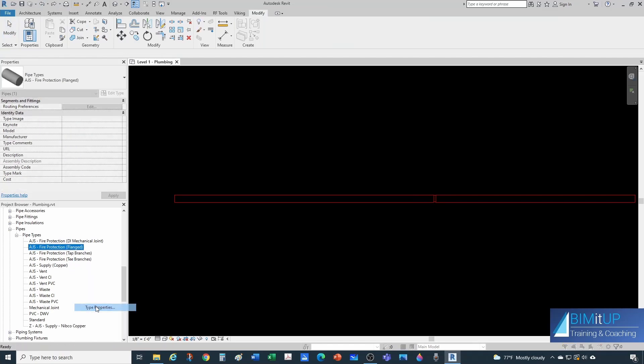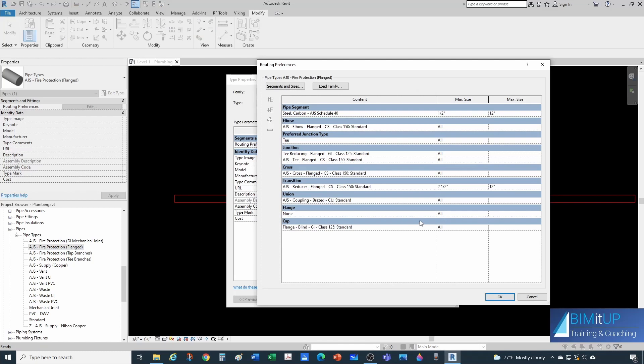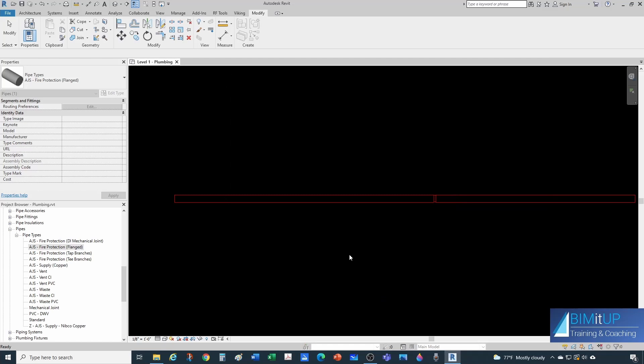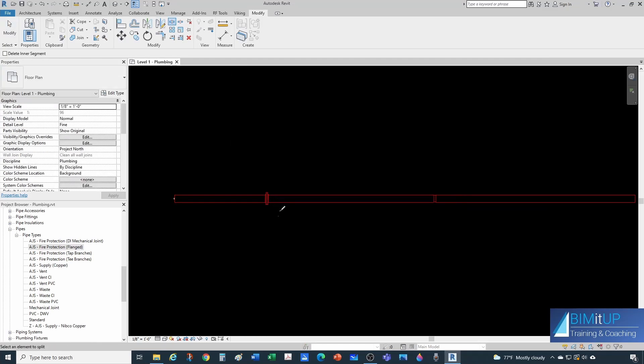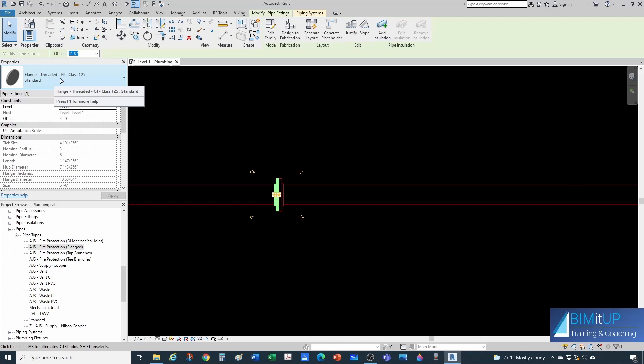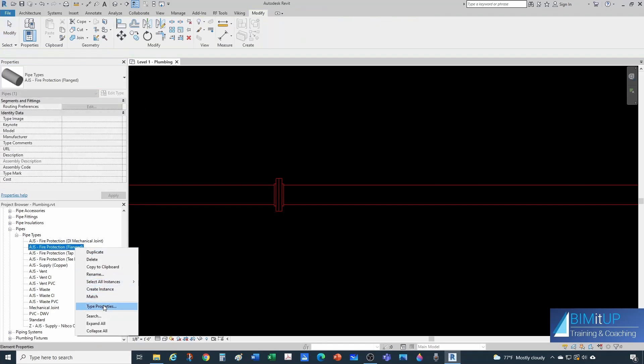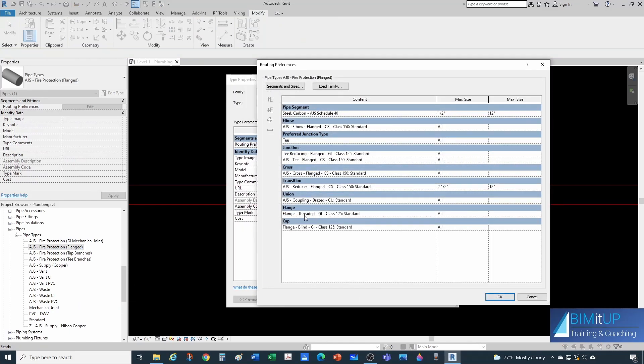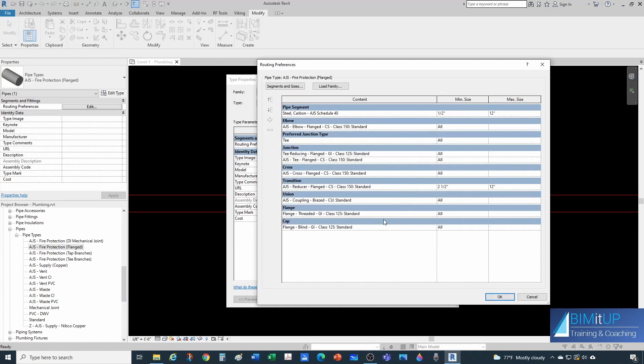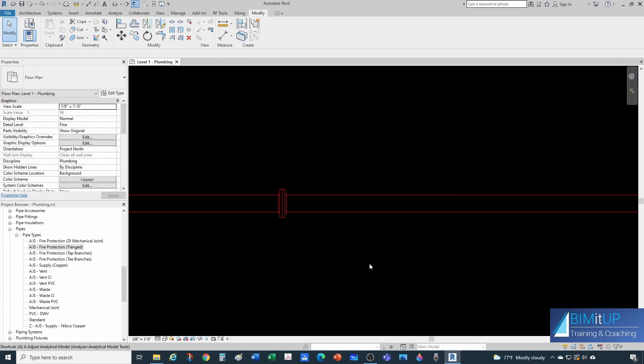Now I'm going to specify a flange — let's use the threaded gray iron class 125. When I press SL for splitting now, notice that what takes precedence is the flange — the gray iron threaded flange. Keep that in mind: whenever you specify a flange, it will always take precedence over the Union. Even if you set the Union field to none, pipe splitting still works because the flange takes precedence.